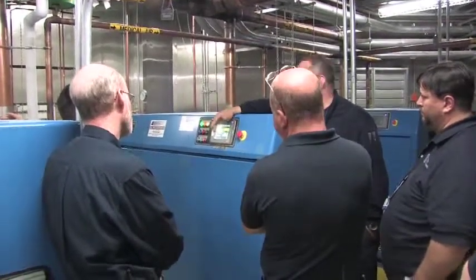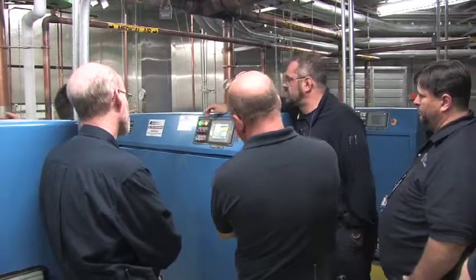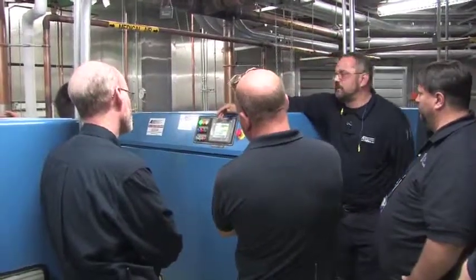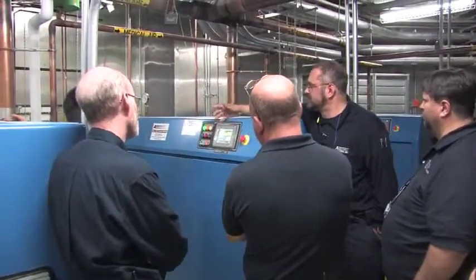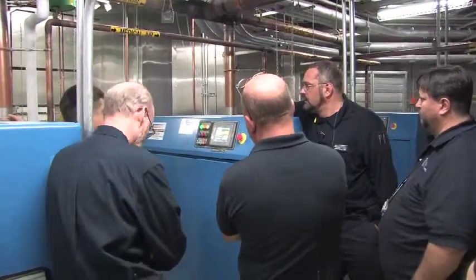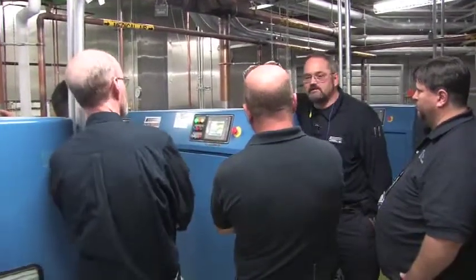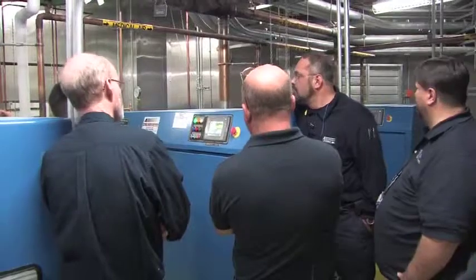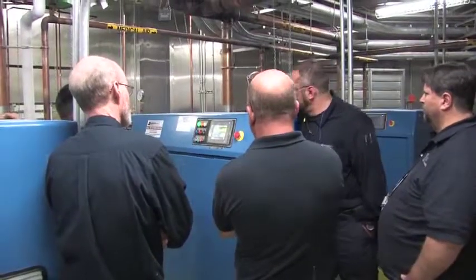Although on machines that top out at 100, it's probably going to be more around 26, 27. But on a high pressure machine, it's possible for that to go all the way to like 42 pounds. That's about as much as you'd ever see on one though. That's on a machine that's going to 150. You might see 42 on the interstage.